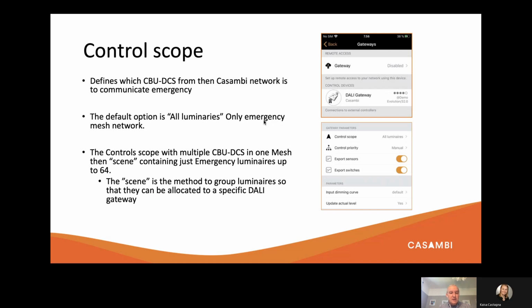So both solutions can mean either you have one single network with only emergency devices inside, or a single network with both standard and emergency luminaires, but the DALI controller would only recognise those emergency luminaires via the DALI gateway device, based on the scene or group that's been set up.